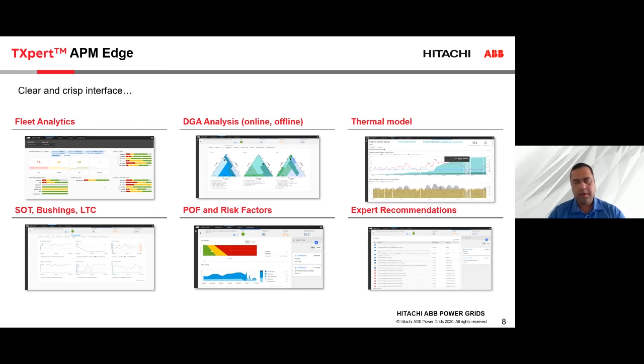And I will give you a case study focusing on the DGA. When we talk about DGA, what we have done here is we have taken into account both online DGA and offline DGA. For offline DGA, we do both gas level and gas trend analysis. And we also take into account what is the accuracy of the lab. And then we calculate if the lab and the online DGA device are differing by X amount, the expert system will automatically tell you that the two are not matching.